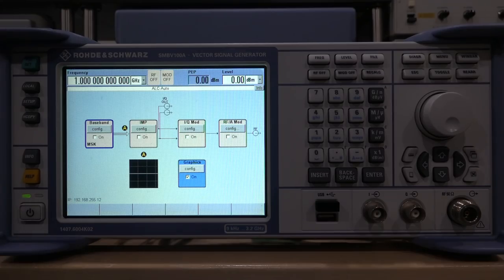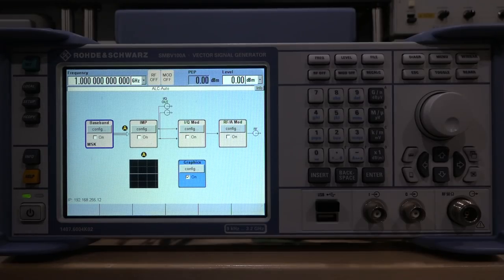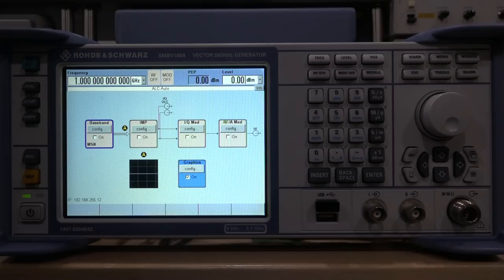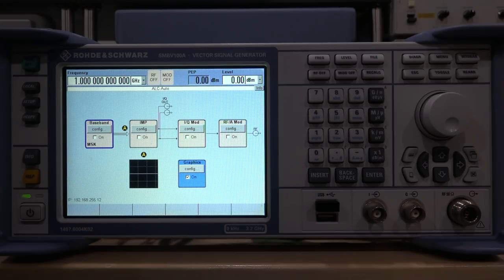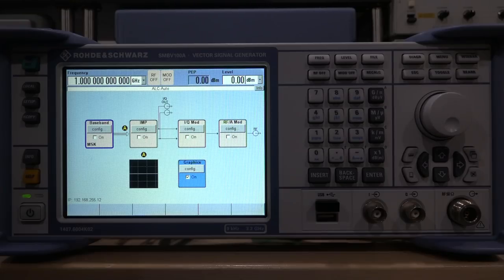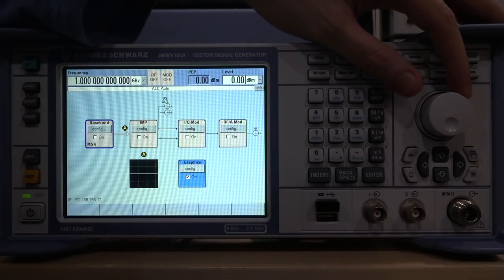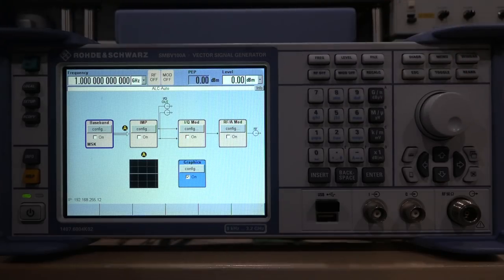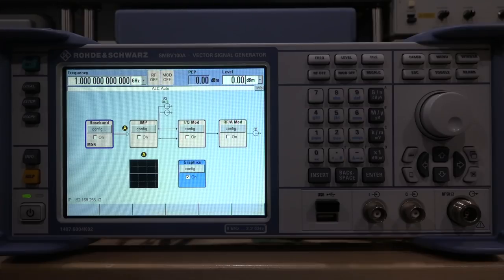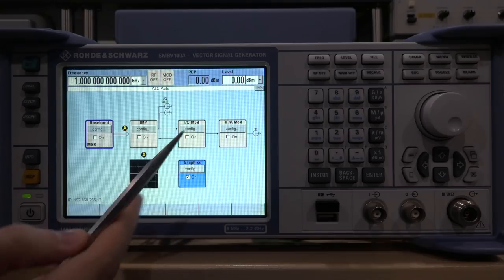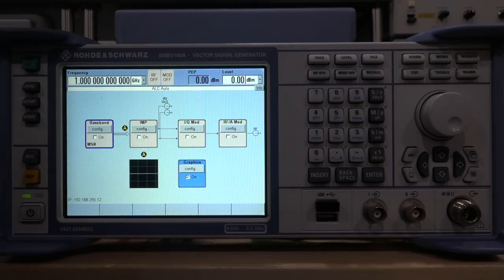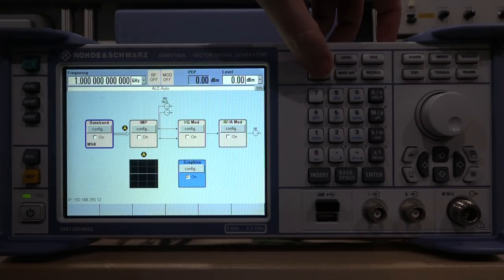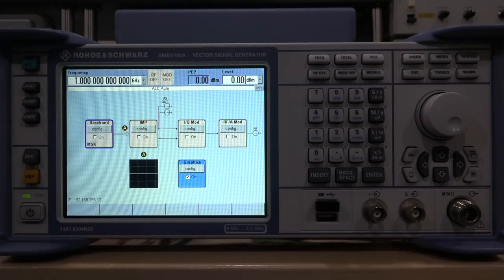So here the instrument has booted and it has the classic signal flow diagram GUI that Rohde & Schwarz has in all of their instruments. It's fantastic. I think it's one of the best ways, really an engineering way of displaying how signal is processed and manipulated and in every step of the way you can then go ahead and adjust various settings. We're not going to make any adjustments or do any modulation. We just want to see a tone out of the unit. Right now it's set to 1 GHz at 0 dBm and the output is turned off. I can enable and disable the output like this. Let's hook it up and see what comes out.